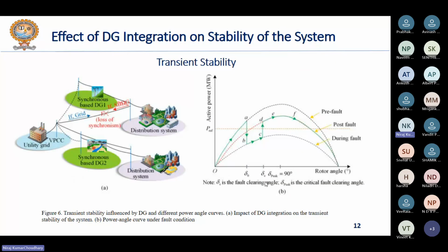Now here, I would like to introduce some other challenges that may occur in any microgrid system, because as we have discussed in the architecture part of the DG microgrid, there may be multiple types of DG connected in the system. Some DGs may be directly interfaced or synchronous machine based DGs, you can say SBDGs, and most of the DGs are electronically coupled or inverter based DGs. So SBDGs have a significant impact on the transient stability of the system. This transient stability, you also know as rotor angle stability.